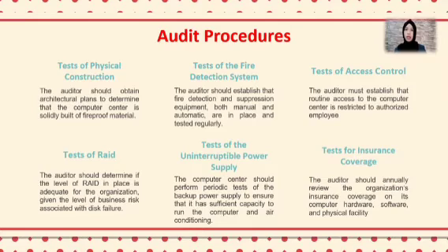Fifth one is the test of uninterruptible power supply. The computer center should perform periodic tests of the backup power supply to ensure that it has sufficient capacity to run the computer and air conditioning. These are extremely important tests and their results should be formally recorded.